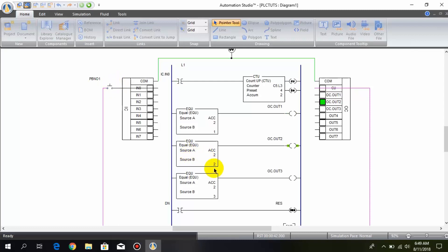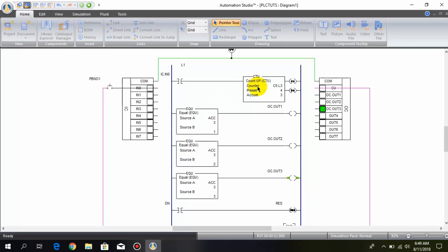The third comparator becomes true and the third output is turned on. When I press the push button the fourth time, the DN bit turns on and resets the counter again.